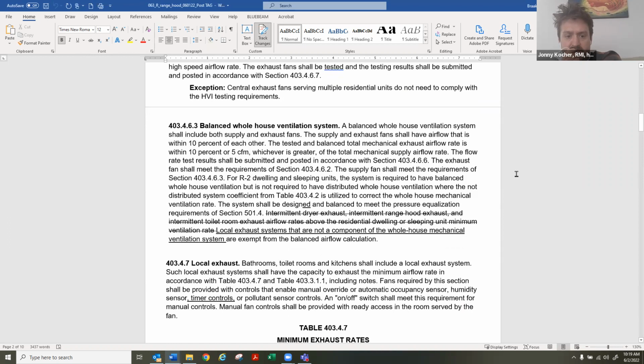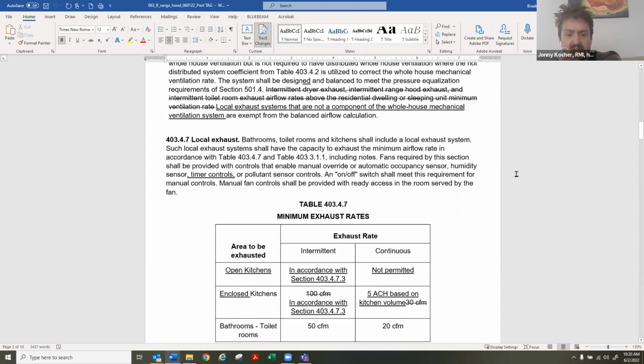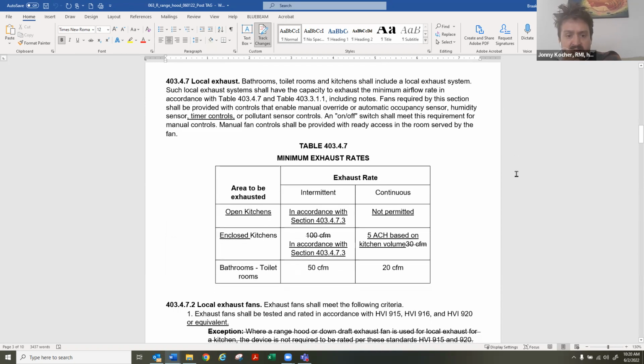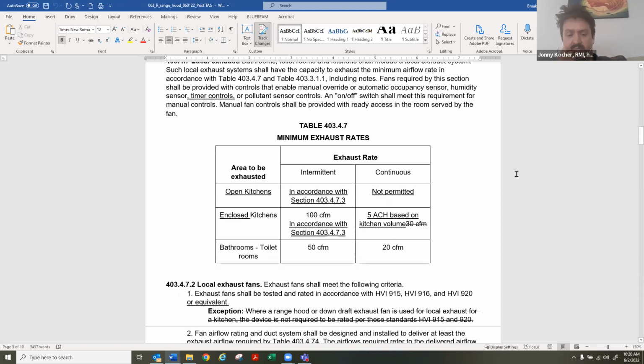403.4.6.3. We broadened the language a little bit. Instead of saying intermittent, we just said local exhaust systems that are not a component of whole house ventilation are exempt from balanced airflow. We added timer controls to 403.4.7. So here's getting more into the meat of it. Table 403.4.7. For open kitchens, we are not permitting continuous exhaust systems. It doesn't particularly make sense for an open kitchen because an open kitchen is open to the rest of the common spaces of the home and won't effectively ventilate the space to get rid of the pollutants.